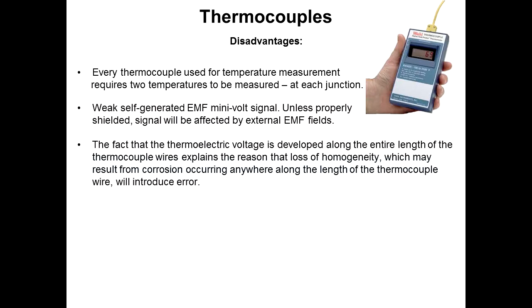The measurement is taken from the sensor across the length of the thermocouple wire, over how long the probe is, and the wiring it's transmitting. So if you have corrosion along that, it will affect the signal. Homogeneity will be affected, especially if you use a thermocouple like a type J, where one of the wires is iron. You'll have a lot of rust problems, corrosion problems along that. So make sure that those are protected from the elements if possible.